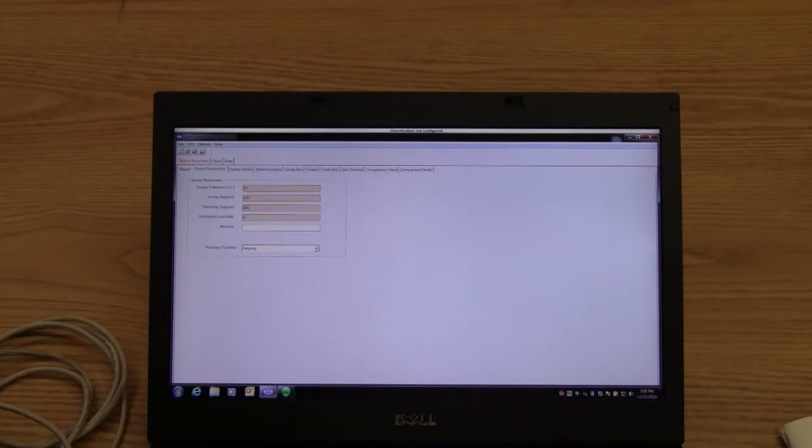If your set point is 920 and your tolerance is plus or minus 10, don't set your over temp for 930, because you just might over temp, especially in your initial ramp up when your oven's not stabilized. That's not a big deal because you don't have your parts in your oven while you're ramping up if your recipe doesn't call for it. So you don't want your oven to shut off. Set it at a reasonable over temp, 30, 50 degrees over, and then you can modify it as necessary as you begin the heat treat process. But 30 degrees is not an unreasonable over temp set point.